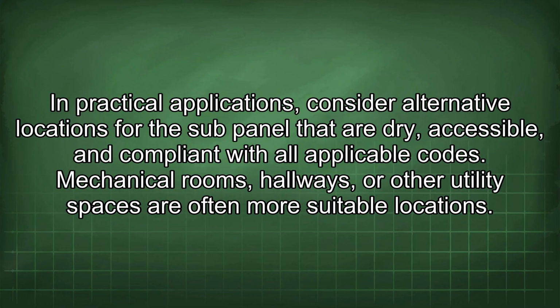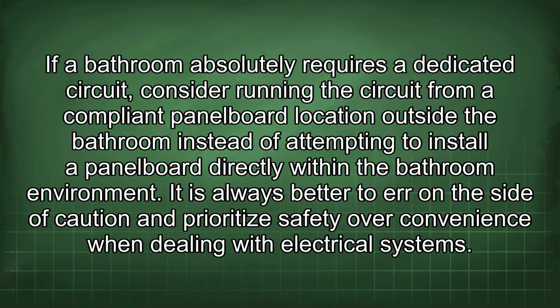In practical applications, consider alternative locations for the sub-panel that are dry, accessible, and compliant with all applicable codes. Mechanical rooms, hallways, or other utility spaces are often more suitable locations. If a bathroom absolutely requires a dedicated circuit, consider running the circuit from a compliant panelboard location outside the bathroom instead of attempting to install a panelboard directly within the bathroom environment. It is always better to err on the side of caution and prioritize safety over convenience when dealing with electrical systems.